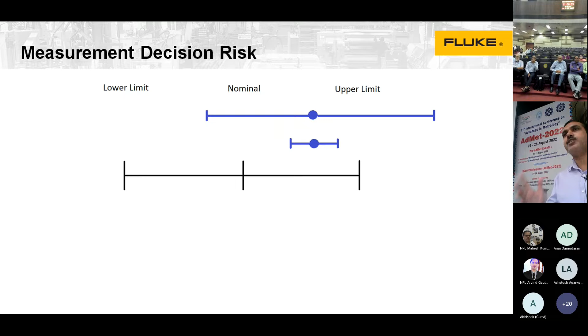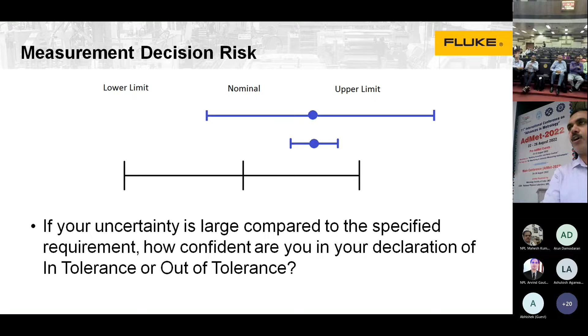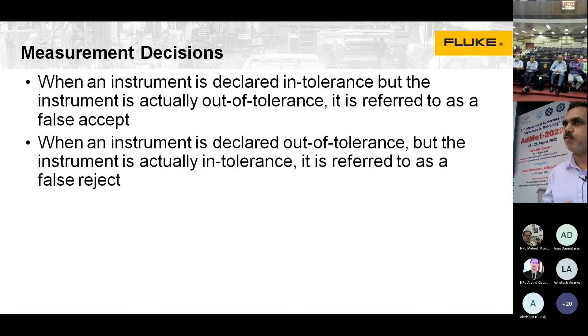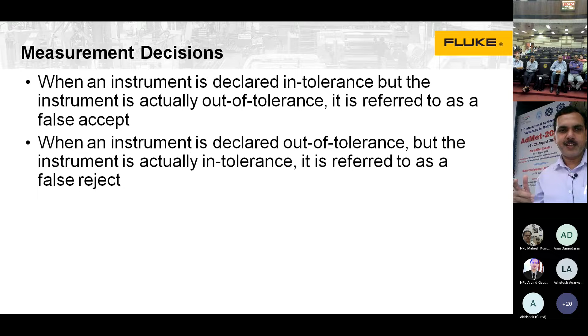So if your uncertainty is large compared to the specified requirement, how confident are you in your declaration of in tolerance or out of tolerance? When an instrument is declared in tolerance, but the instrument is actually out of tolerance, it is referred to as a false accept. And when an instrument is declared out of tolerance, but the instrument is actually in tolerance, it is referred to as a false reject. This false accept is the consumer's risk, and false reject is the manufacturer's risk.